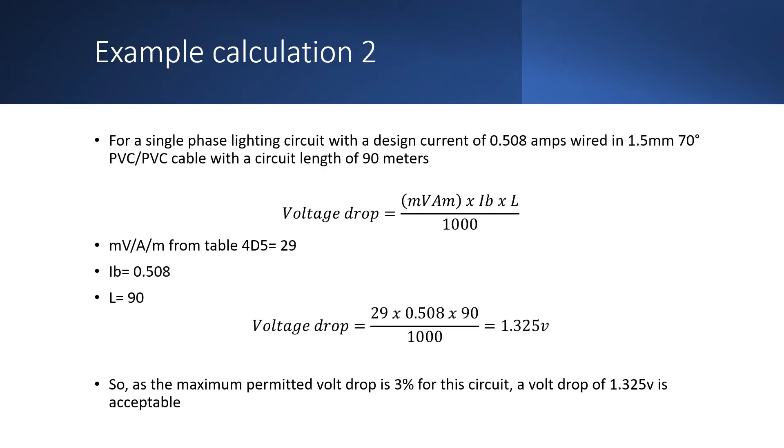So here we have another example, this time for a lighting circuit. For a single phase lighting circuit with a design current of 0.508 amps wired in 1.5mm 70 degree PVC-PVC cable with a circuit length of 90 meters. So the value for millivolts per ampere per meter is taken again from table 4D5 and that comes to 29. The design current is 0.508 and the length of the circuit is 90.